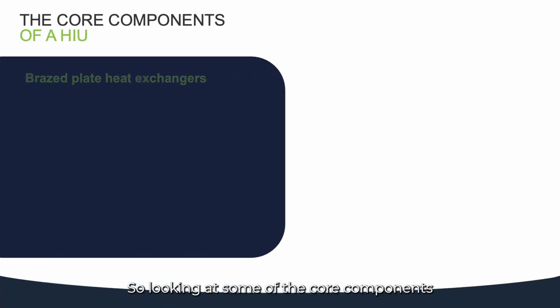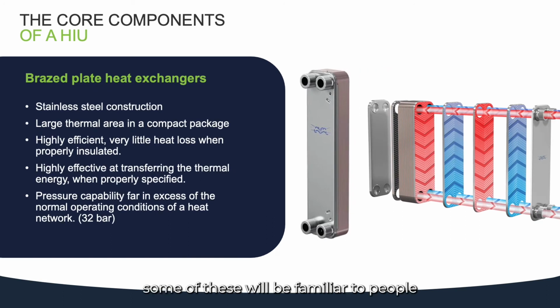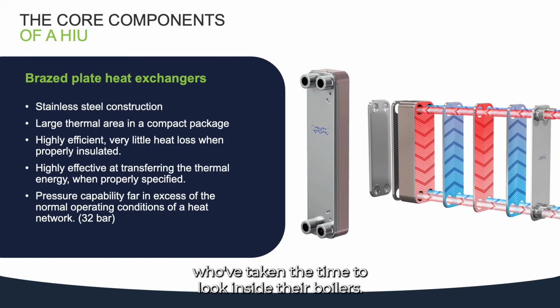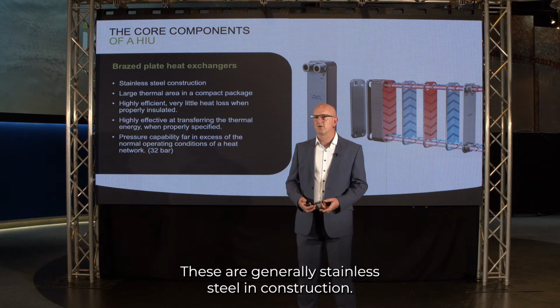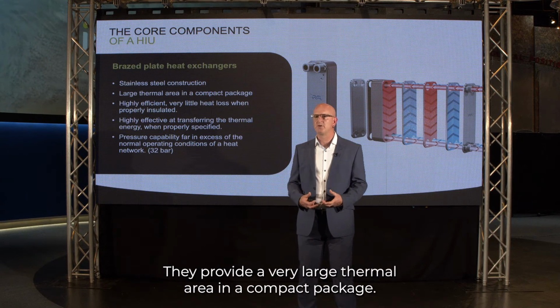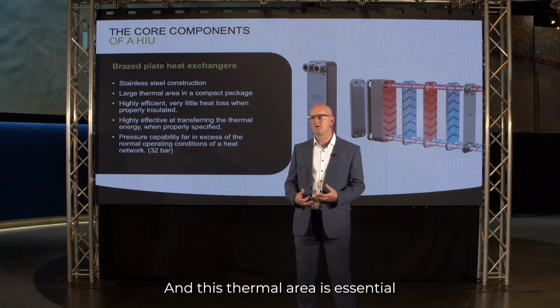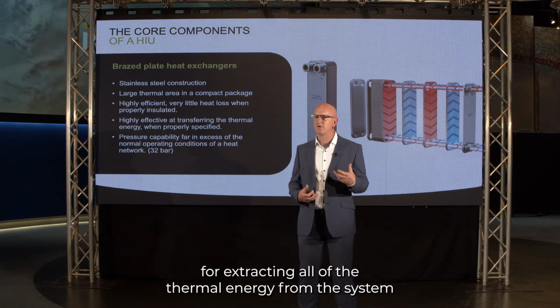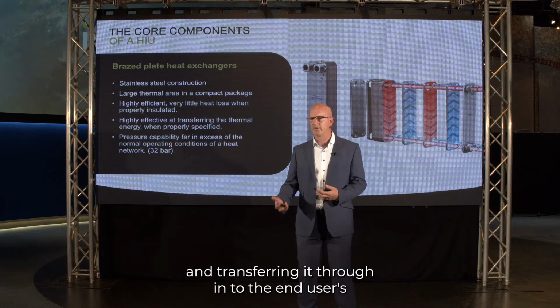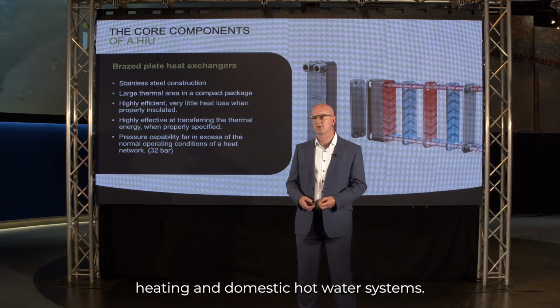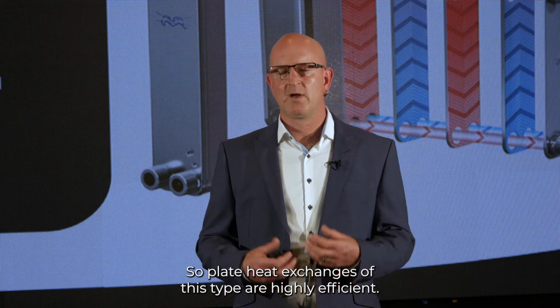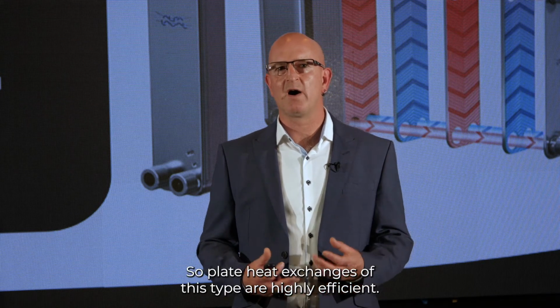So looking at some of the core components of a heat interface unit, some of these will be familiar to people who've taken the time to look inside the boilers, and some of these will be new and introduced with the heat interface unit. So one of the core components at the heart of the appliances are the plate heat exchangers. These are generally stainless steel in construction. They provide a very large thermal area in a compact package, and this thermal area is essential for extracting all of the thermal energy from the system and transferring it through into the end user's heating and domestic hot water systems. So plate heat exchangers of this type are highly efficient.